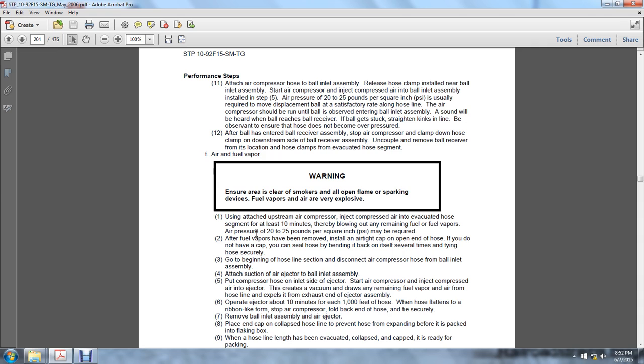Going to the beginning of the hose line section, disconnect the air compressor hose line from the ball inlet. Attach the suction hose on the air ejector of the ball inlet. Position the compressor hose on the inlet side of the ejector. Start the air compressor, injecting compressed air into the ejector. This creates a vacuum and draws any of the remaining fuel vapor and air from the hose line, expelling this from the exhaust end of the hose ejector assembly. Operate the ejector about 10 minutes for every 1,000 feet of the hose.